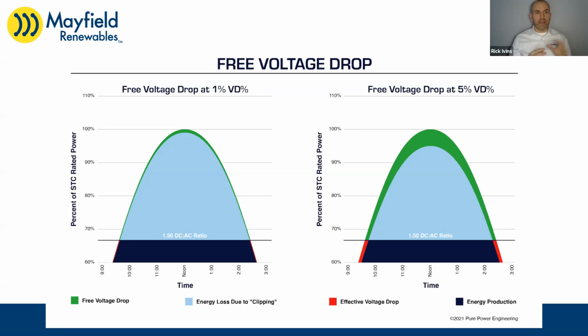If the contract has a particular limit on voltage drop that seems contractually arbitrary, like 1% or 2%, and you have a high DC to AC ratio, you might spend a lot of money on conductors trying to get to that 1% voltage drop where it will never pay back. All you're saving is those little bits on the shoulders at the start and end of the day, or in the middle of the day when clouds pass and you're not at full inverter output. So it becomes really difficult to get a return on that investment of upsizing the conductors.